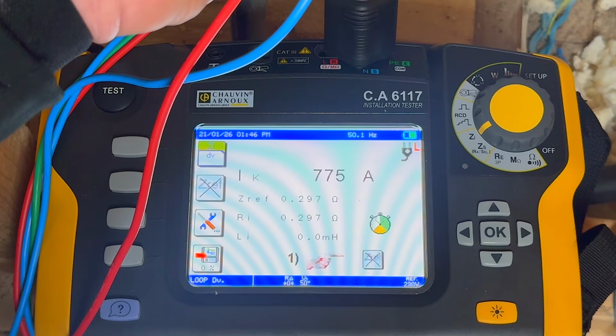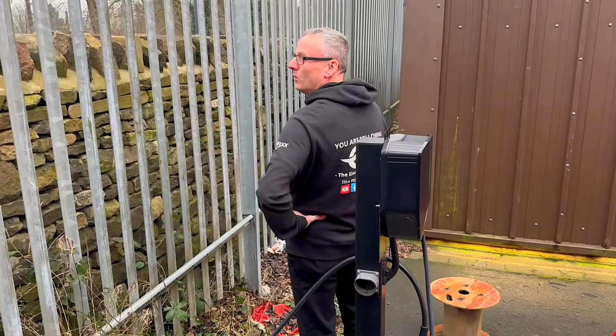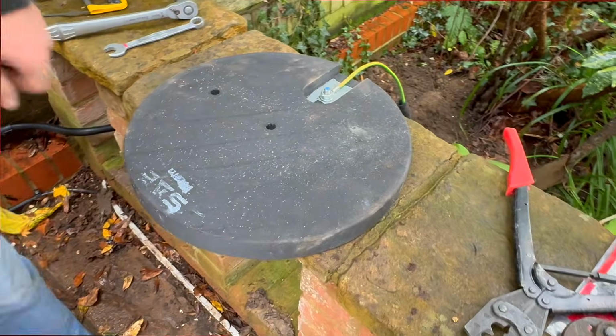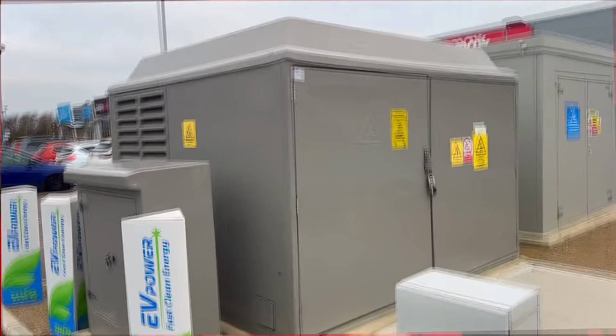and answering some of the most common questions that we see, like why can't we just do an earth fault loop test and call it done? Can getting the electrode wet actually improve the readings? Can this disc really be as good as driving in a rod? And can you slap a substation anywhere? And all of that is to come.